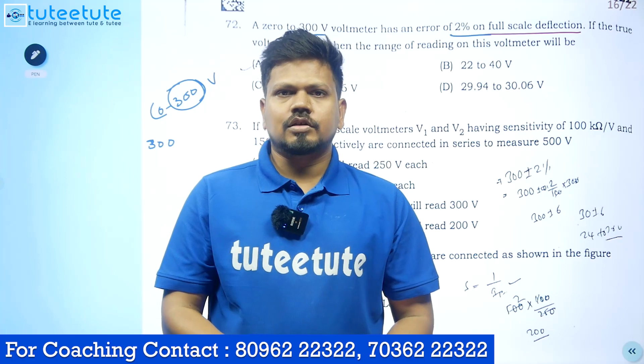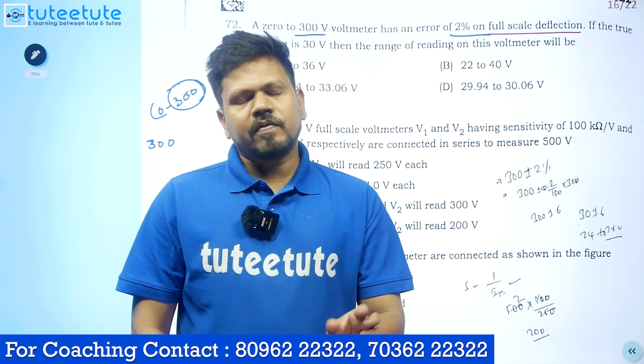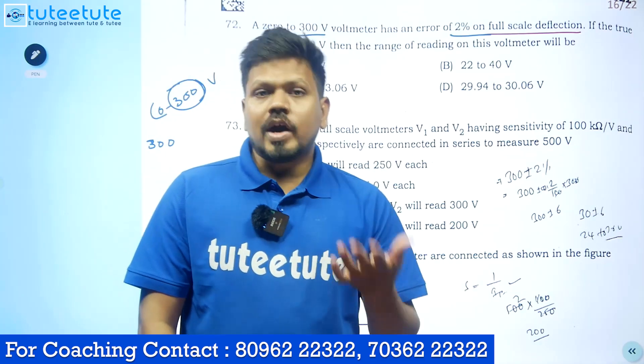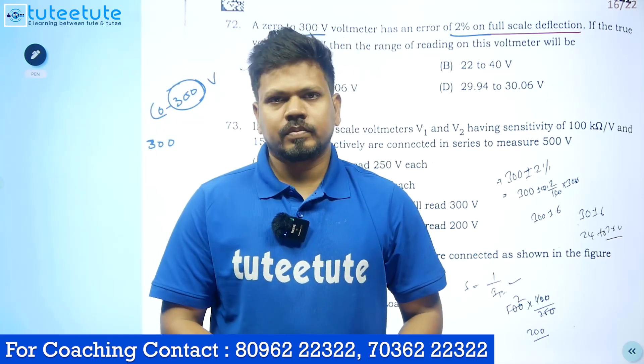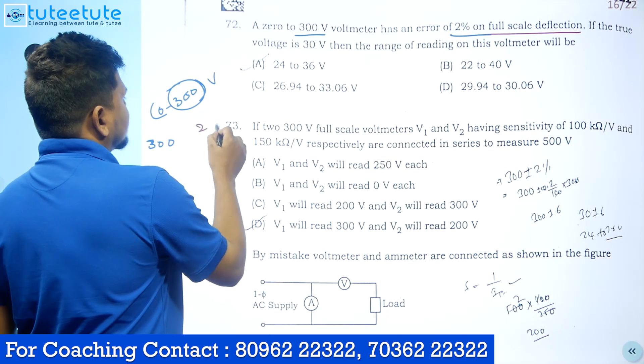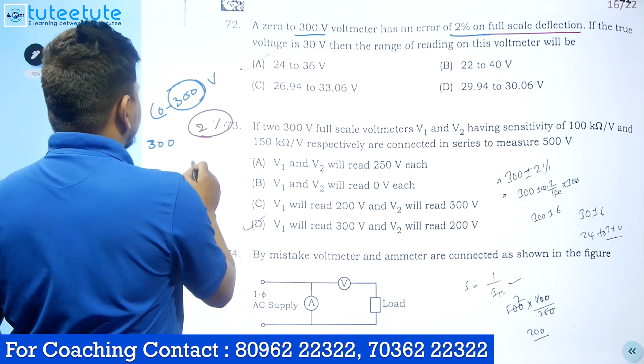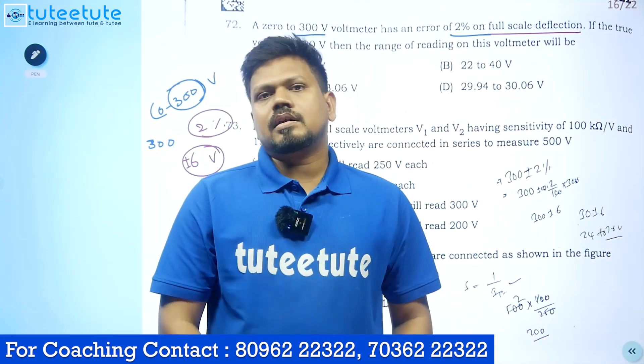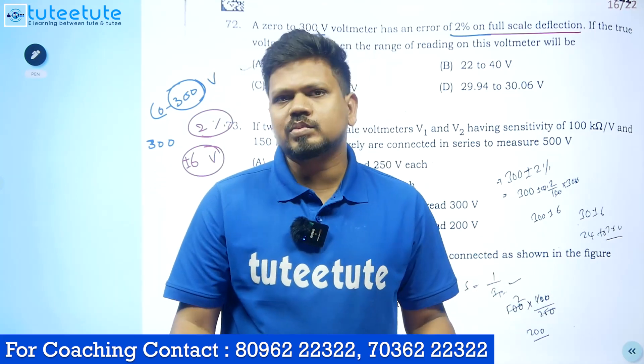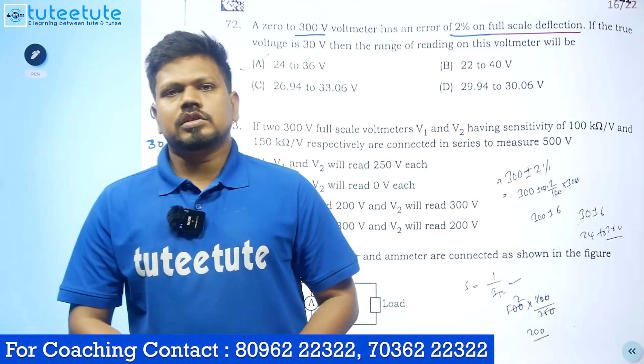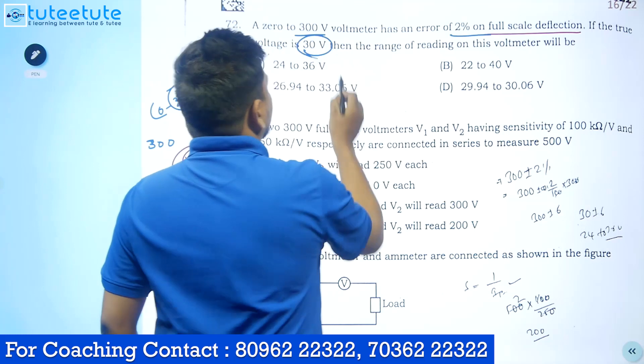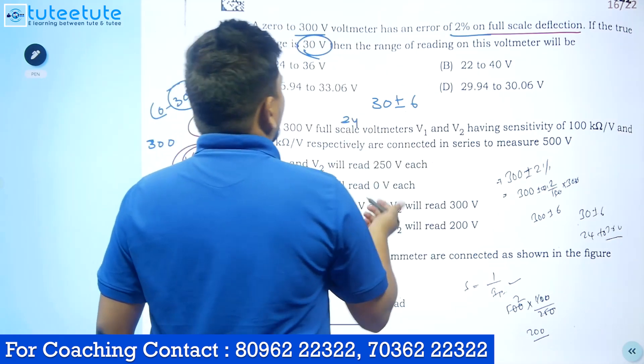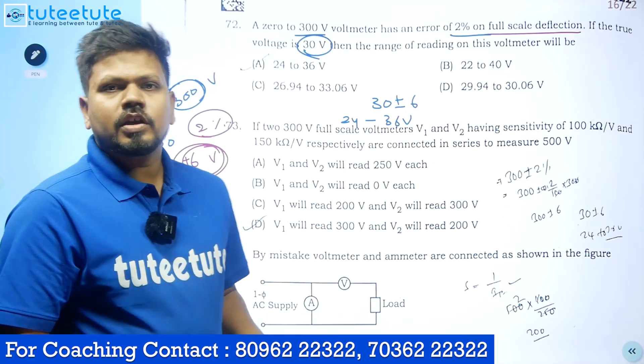Whatever reading this voltmeter is measuring, whether one volt, two volt, or any volt, the error you will get is 2 percent on the full scale. So calculate 2 percent of 300: that is 6 volts. Plus or minus 6 volts will be the guaranteed error. Now it is measuring 30 volts, so it will measure 30 plus or minus 6, meaning it will measure from 24 volts to 36 volts.